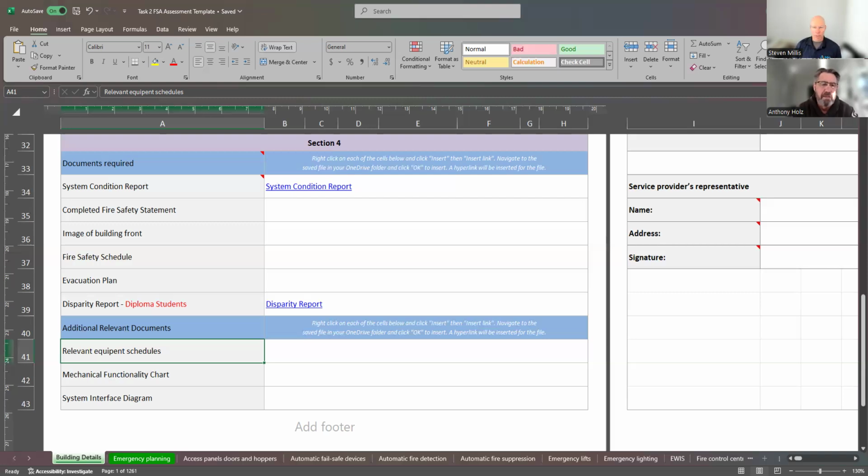in the assessment process. And let's face it, AS 1851 is fast becoming a legal document, and in almost all of the measures, it requires you to create a schedule if there's not one there, especially for valves and gauges and stuff like that with hydrants and wet systems. Even smoke detectors and stuff like that. Like, where are they? Emergency lights, where are they?